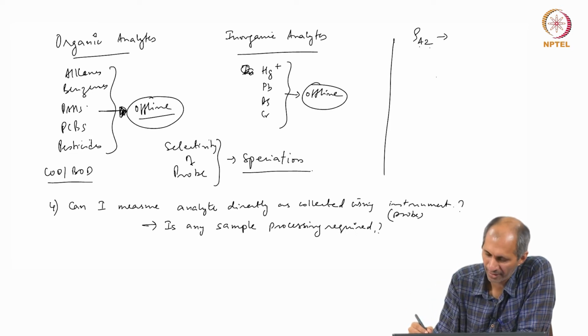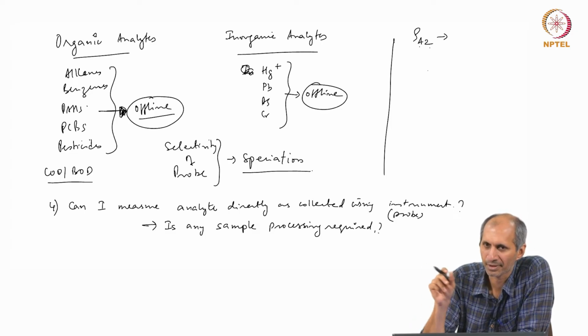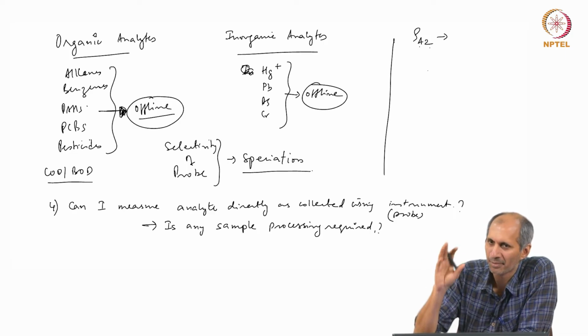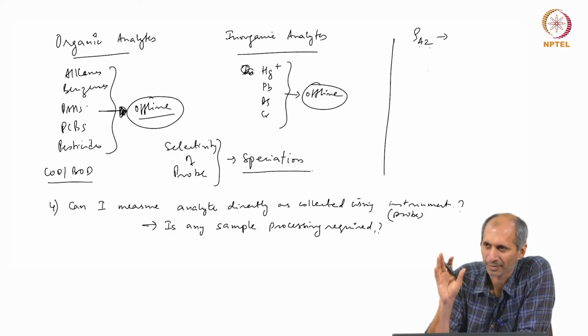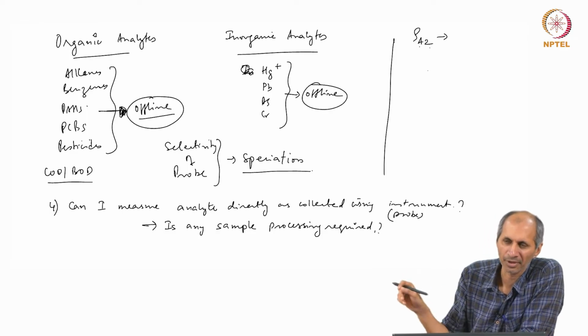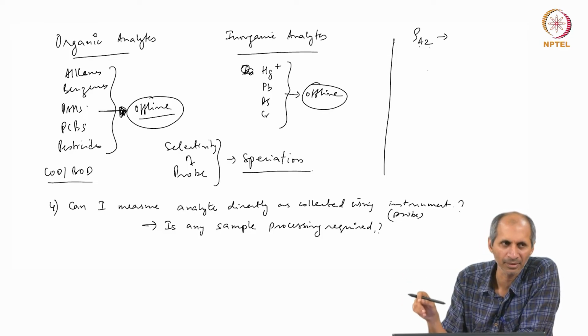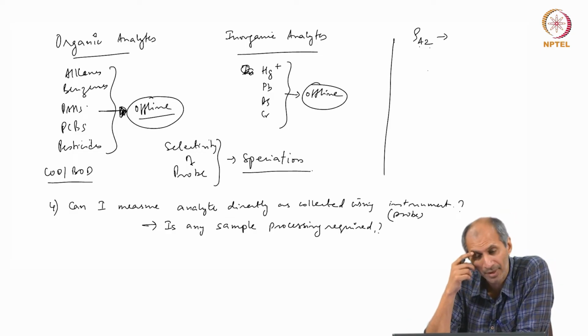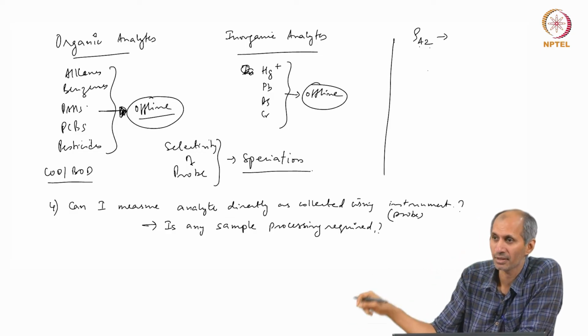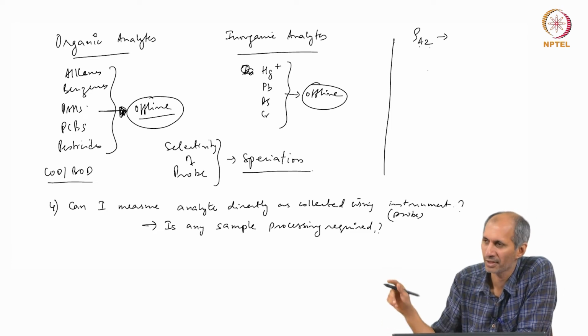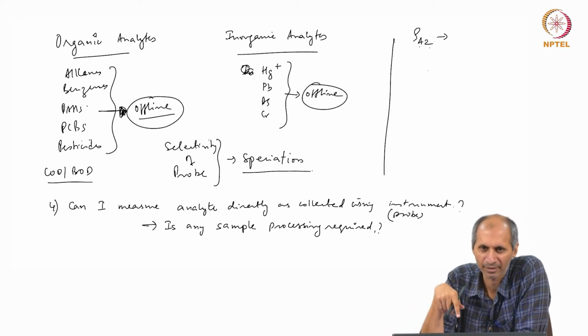All the probes have a certain principle of operation. The pH meter is an electrode system. It's an electrolytic cell. There is a small membrane or a junction somewhere. At one end is the concentration of hydrogen ions and at the other end is something else, so it looks at the potential difference between these two. For that to occur, it needs clear contact across the junction between the analyte of interest and whatever is inside.